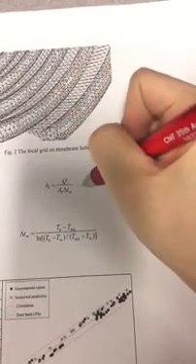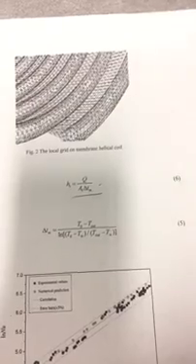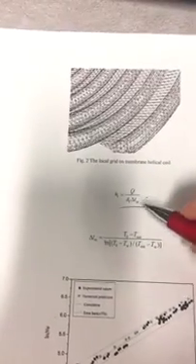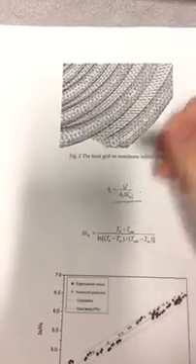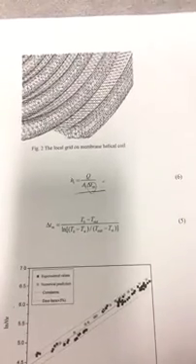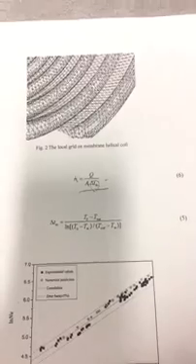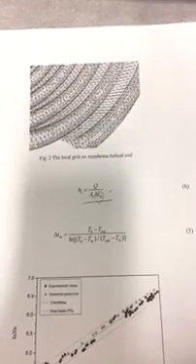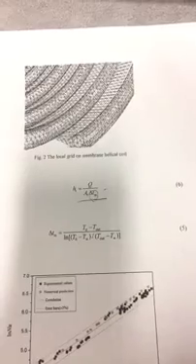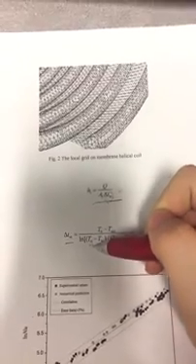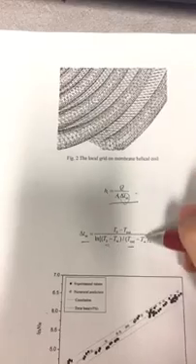This figure 6 is the surface heat transfer coefficient, which was calculated from the inlet and outlet temperature data and the flow rate. Delta Tm is the logarithmic mean temperature difference, and the surface heat transfer rates were based on the outer surface area of the membrane helical coil or membrane serpentine tube. The delta Tm was calculated based on the syngas inlet temperature T0, the outlet temperature T out, and the wall temperature T wall. So we calculated according to this.